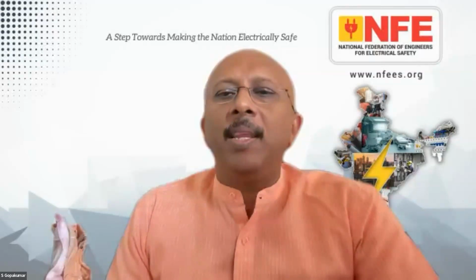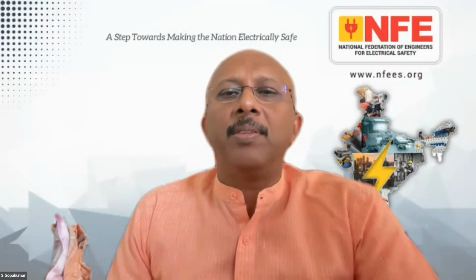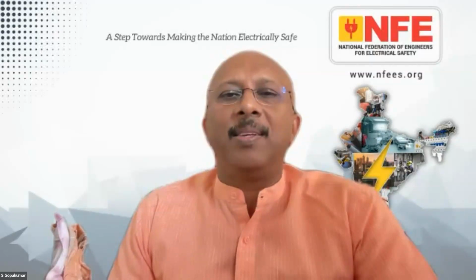One question to Mr. Nitin. How to measure fault loop impedance? In case of a fault loop impedance test, there are devices available called multifunction testers. Depending upon the type of system you have, the TN-S or the TT system, in both cases the multifunction tester can be used to do the fault loop impedance test. It has to be done across one phase and the earth at a time, and you have to measure across all three phases.